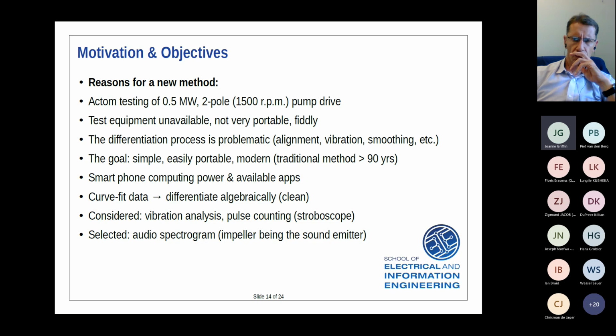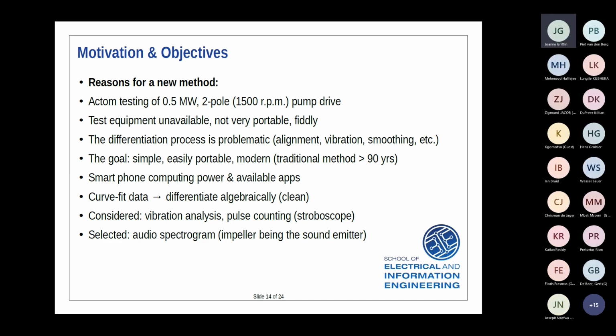Okay. A contributing factor is that the differentiation via hardware is quite problematic because it's very sensitive to the environment, as I said already, to any kind of vibration. So if the machine's vibrating on the test bed or the test bed itself is vibrating, it becomes quite difficult, and you have to employ quite a significant smoothing process to pull out all that artificial noise and focus on the measurement on the rates that you've actually recorded.